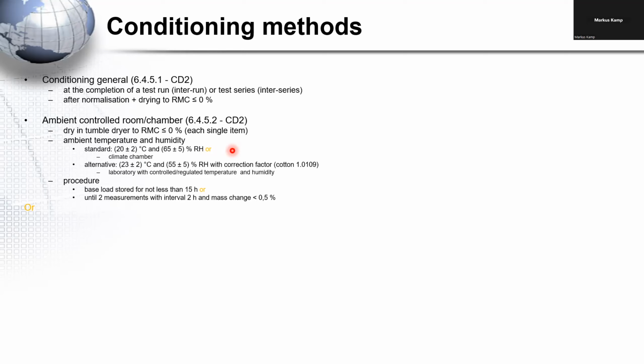Normally, you have a device which is controlling the climate, a big box which is attached to the climate chamber. There are temperature and humidity sensors inside. It is not recommended to use these devices or these sensors because they are normally hard to reach. And the question is, how can you calibrate these devices? Because the devices you are using for measuring the temperature and the humidity have to be calibrated regularly, so that it's guaranteed that your measurement data are okay.